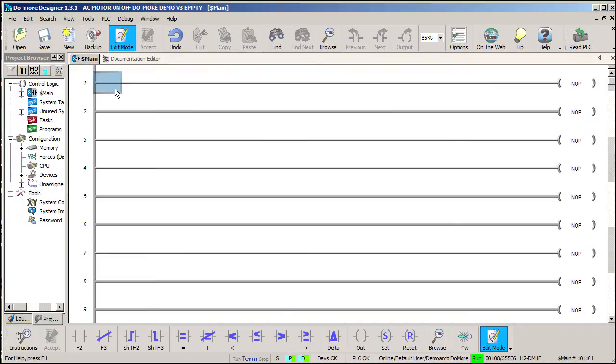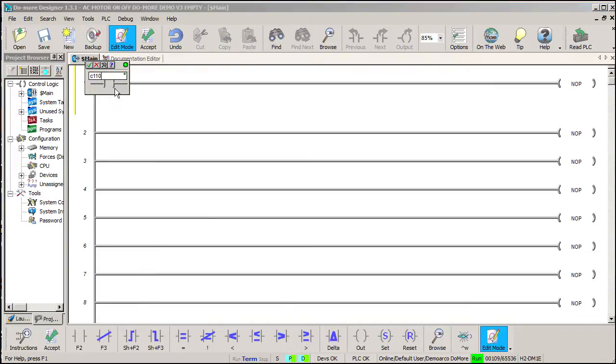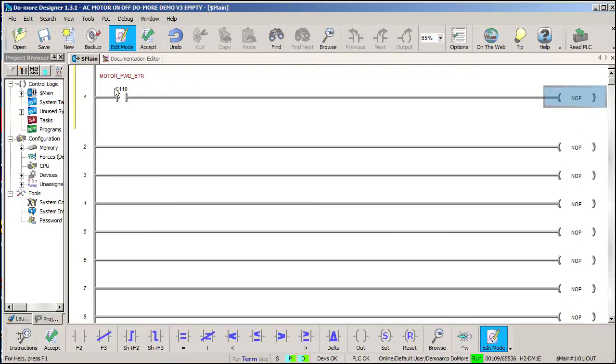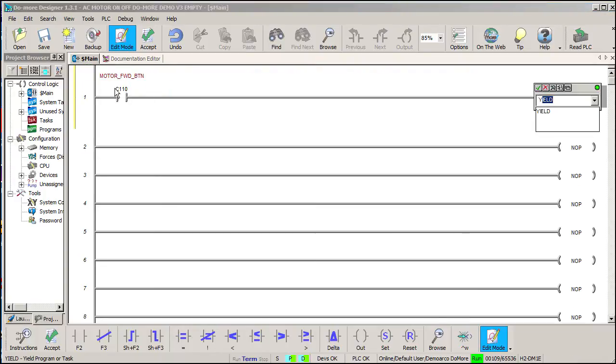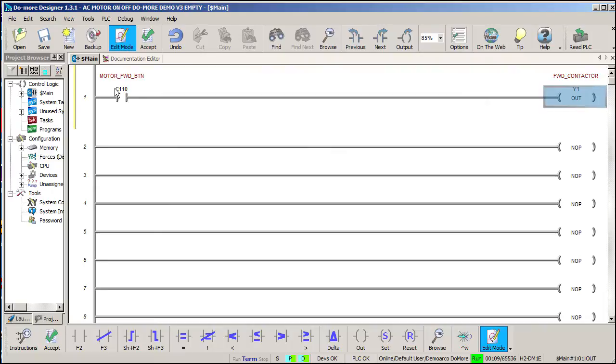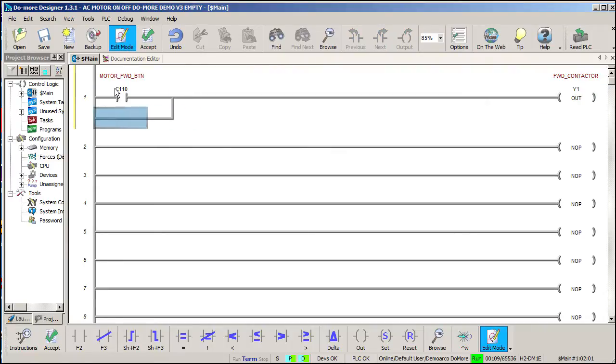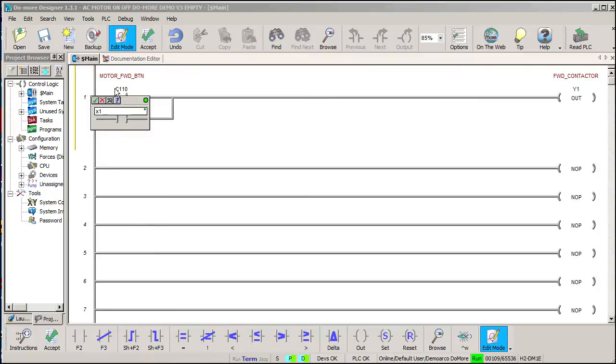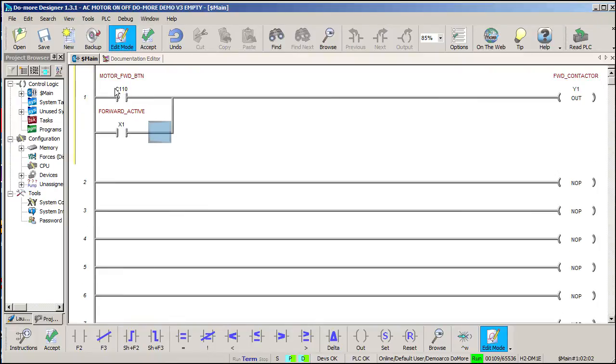Let's get the motor running in the forward direction. So on a button press, our virtual C-more HMI button in this example, enable the forward contactor which is output Y1 in our setup. And once that forward contactor is engaged, the AUX contact closes so we can use that to keep the motor running even after the momentary forward button is released. We call this sealing or latching the contact.